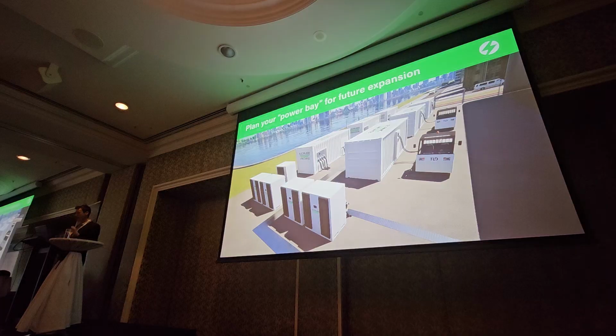This is what I mentioned about power bays. If you start going beyond a megawatt, or even about half a megawatt, you start needing to plan your AC to DC infrastructure, with containerized batteries and, in this case, the AC to DC cabinets. You need some real estate, usually ground side rather than air side, then running the DC cables into the air side is the better use of land space.